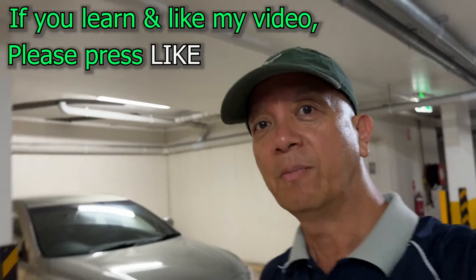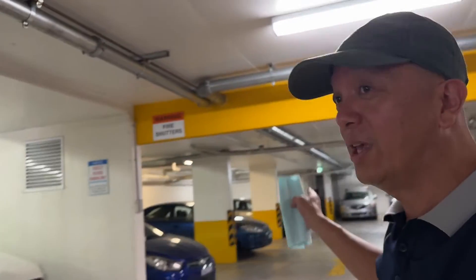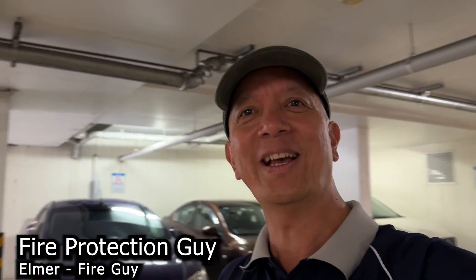You must be aware that different building sites have different procedures and different types of hydrant diesel and hydrant pump controllers. There are buildings where you cannot do your test after 8 o'clock in the morning — you can only do it around 6 AM, especially those with offices. In this case it's a residential building so I can do my test after 8 o'clock. I hope you learned something today — this is Elmer, your fire protection guy. See you next time.